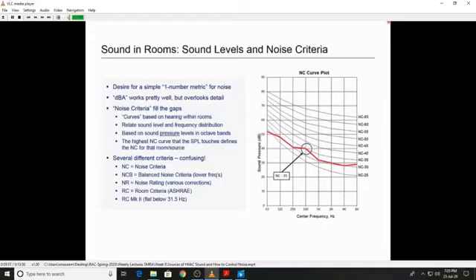If it's lower, people are less annoyed. If it's higher, people are more annoyed. But that doesn't really describe the timbre or quality of the noise, its frequency spectrum content. And so we use noise criteria curves, and so you'll often hear about NC ratings. These are curves based on how people hear sound in rooms. They relate the sound level and the frequency distribution. We take the sound pressure level in octaves and map it out on a chart against these curves, and we note wherever the spectrum touches the highest numbered curve, that's the NC level.